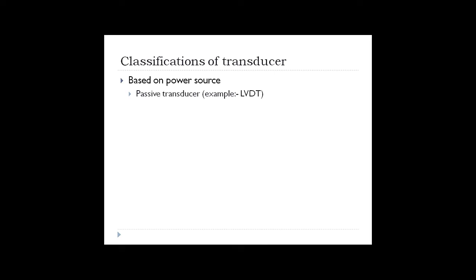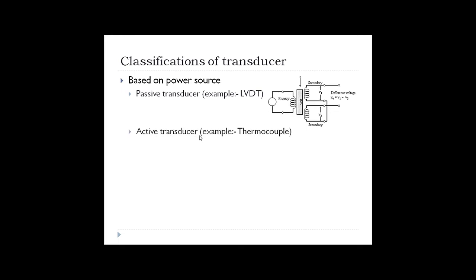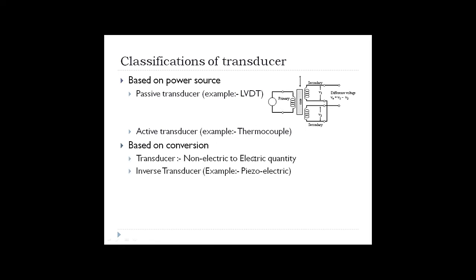Classifying transducers based on power source: a passive transducer needs an external power supply for its operation — for example, an LVDT (Linear Variable Differential Transformer) needs a power source. An active transducer does not need any power source for its operation. For example, a thermocouple works on the principle of the Seebeck effect, where thermoelectric EMF is generated when two bimetals are connected together. No external supply is needed to generate this thermo-EMF in a thermocouple.